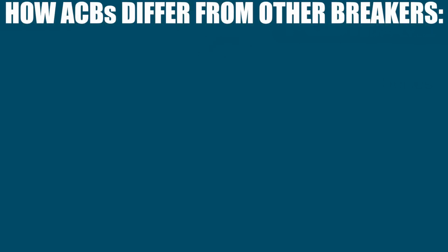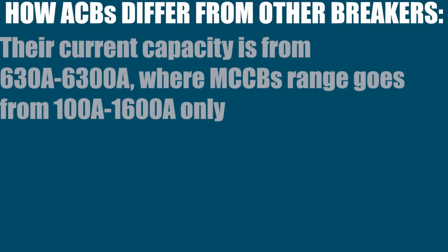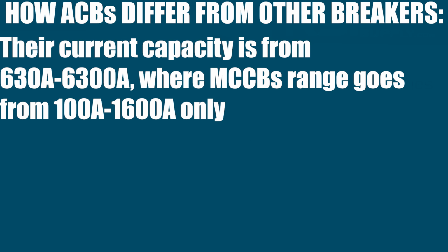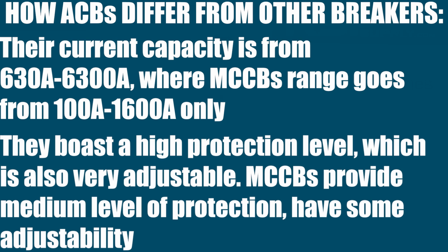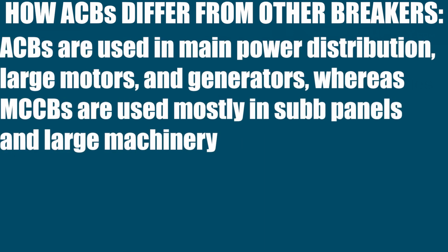So how do ACBs differ from other breakers? One of the biggest differentiators is their current capacity. It goes from 630 amps on the low end all the way up to 6,300 amperes, where a molded case circuit breaker range goes from 100 amps to 1600 amps only. They also boast a high protection level, which is also very adjustable. MCCBs provide a medium level of protection, with some adjustability. Air circuit breakers are used in main power distribution, large motors, and generators, where molded case circuit breakers are used mostly in sub-panels and large machinery.